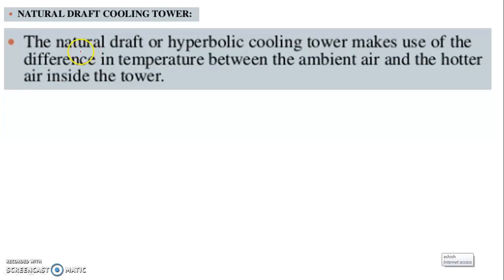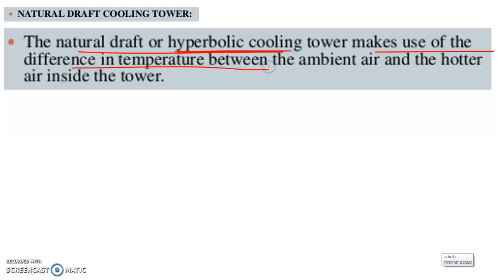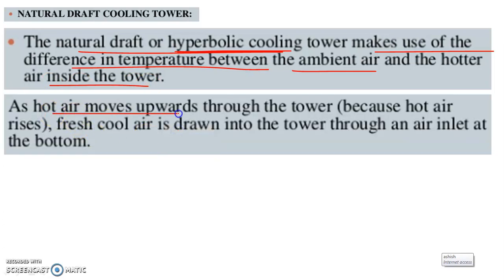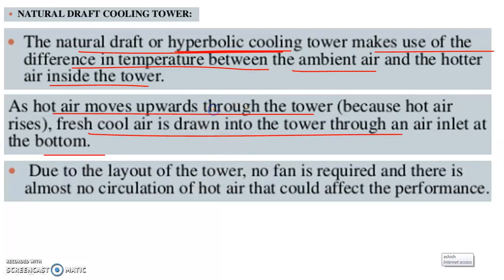The natural draft, also called the hyperbolic cooling tower, makes use of the difference in temperature between the ambient air and the hotter air inside the tower. As hot air moves upward through the tower — since hot air rises — fresh cool air is drawn into the tower through an air inlet at the bottom. Due to this layout, no fan is required and there is almost no recirculation of hot air that could affect performance.